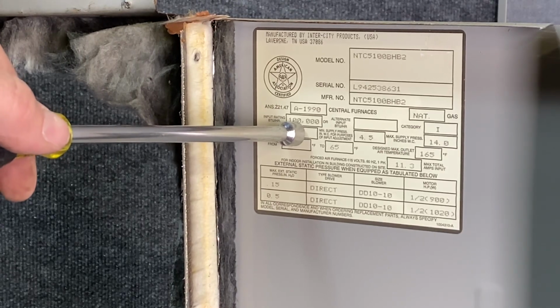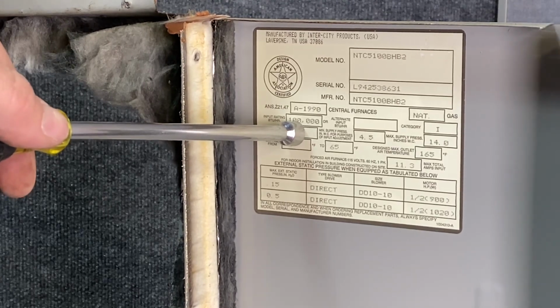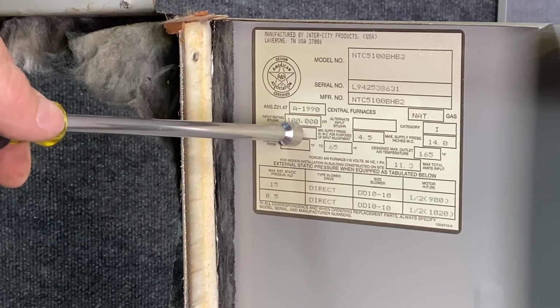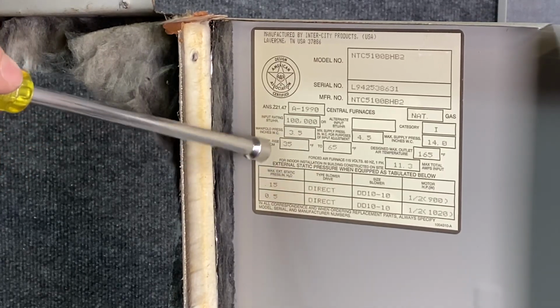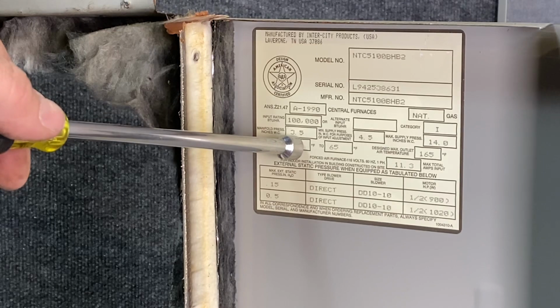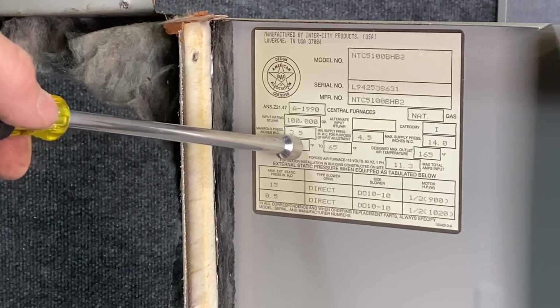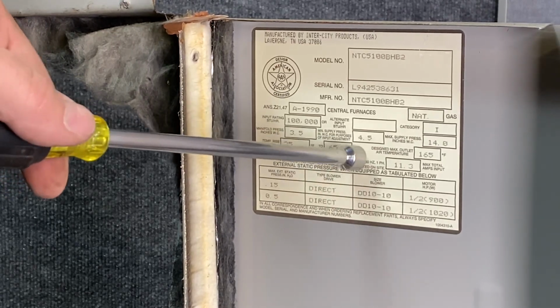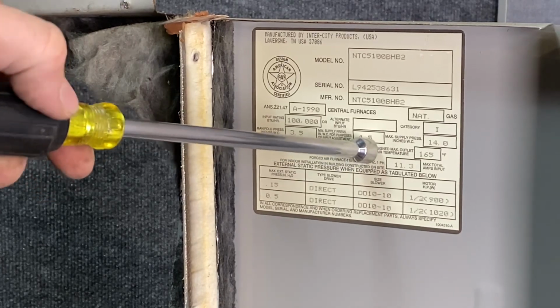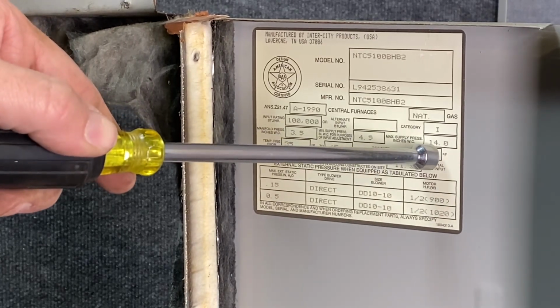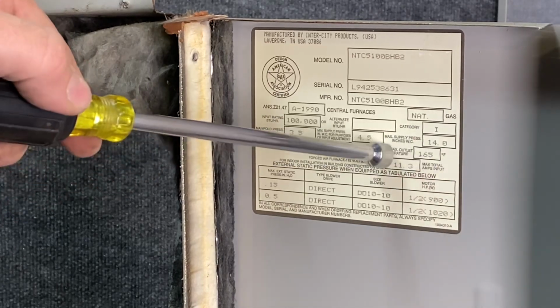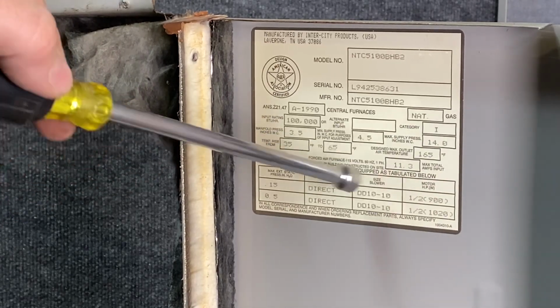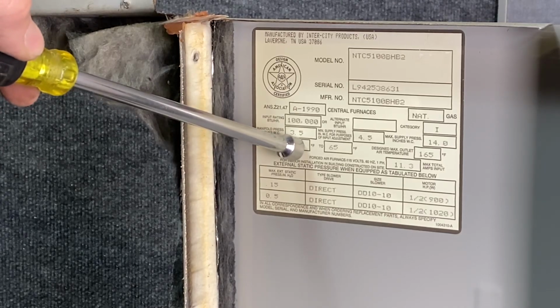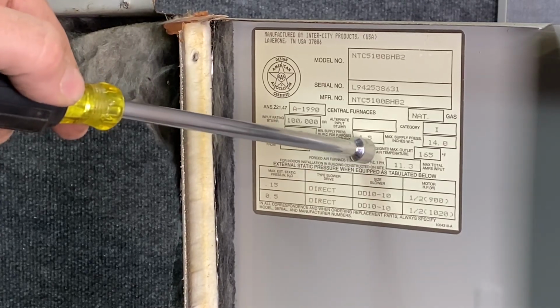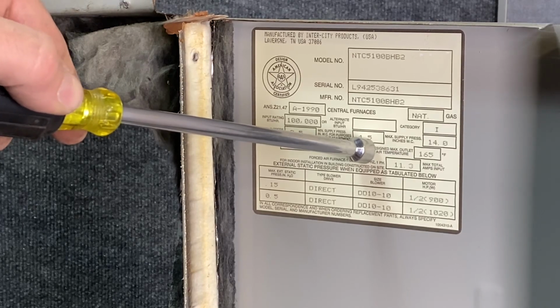Otherwise, if I put a 90+ furnace in here, also 100,000 BTU, we'd be over by 20,000 BTU, and you never want to oversize a gas furnace or any air conditioning system. The manifold gas pressure, 3.5 inches of water column on the manifold side. And the minimum supply pressure input is 4.5 coming in, and a maximum of 14 inches water column coming in. So you have that range of pressure coming in. So if you have an issue to where your output is not getting high enough, check the input while other things are running, such as the stove or the water heater.